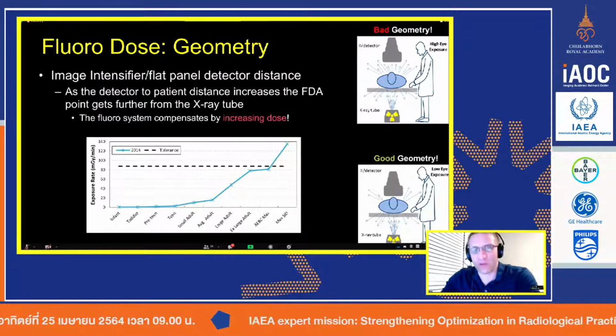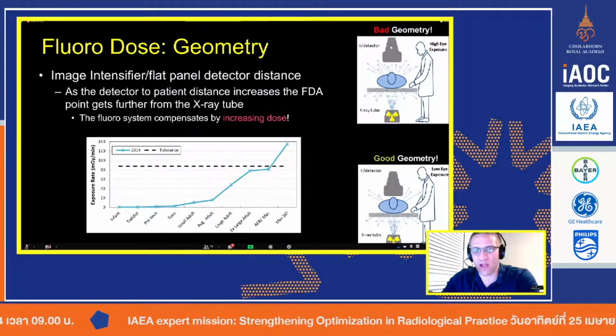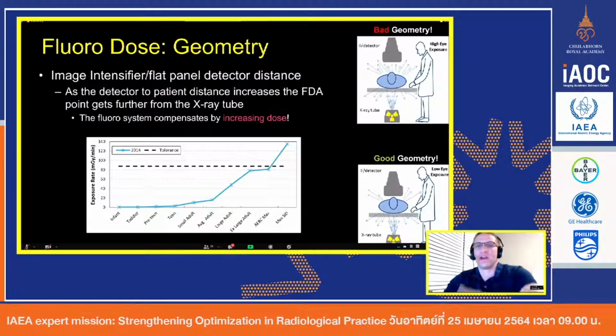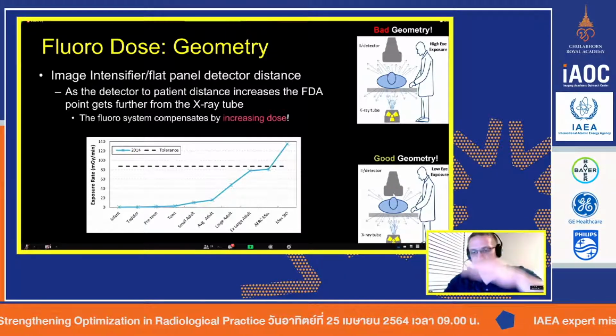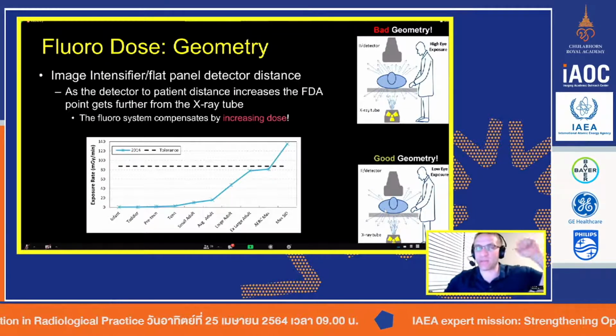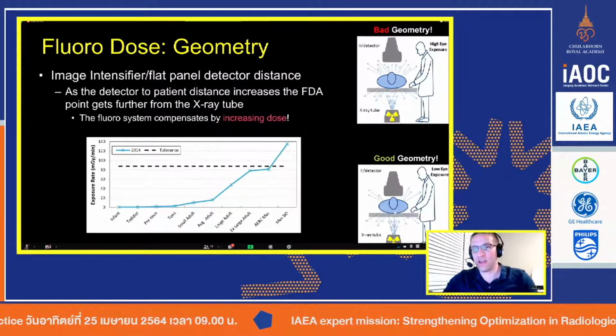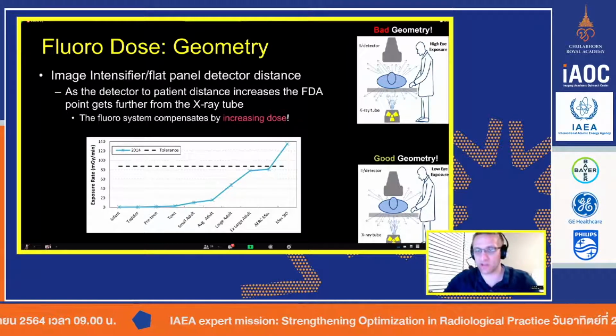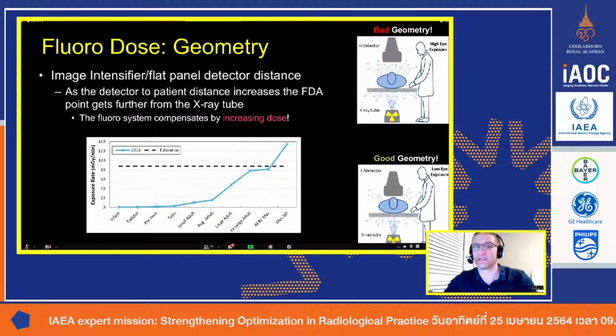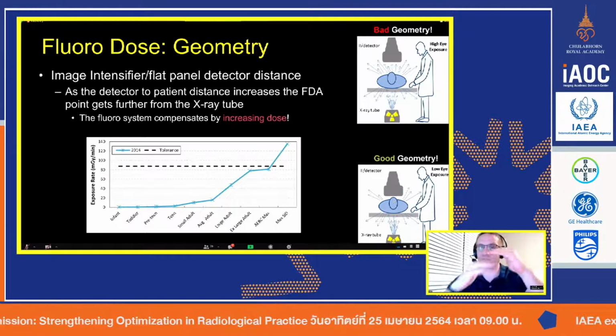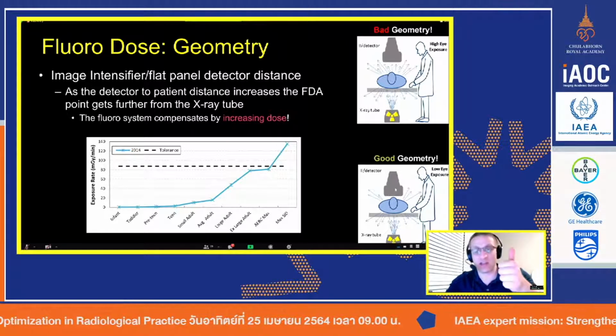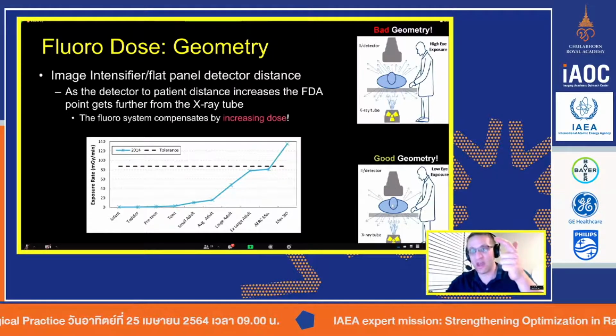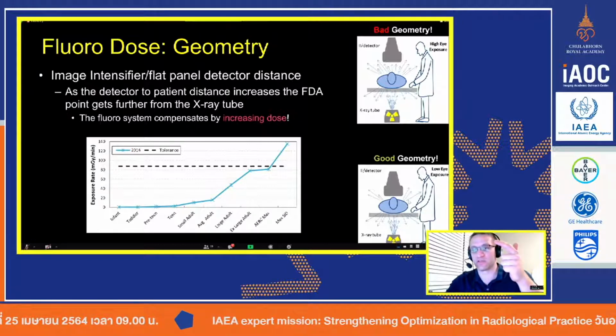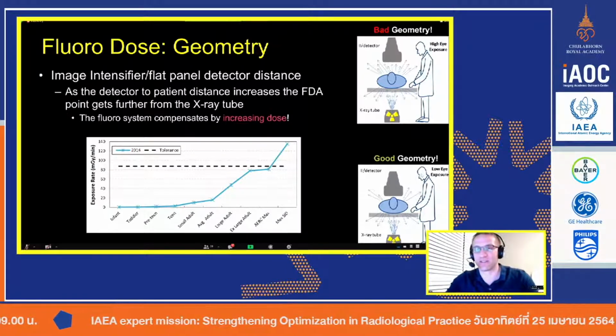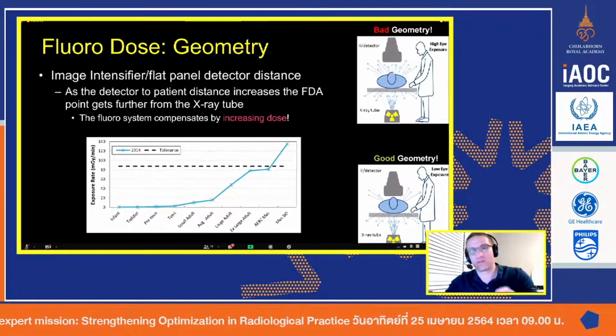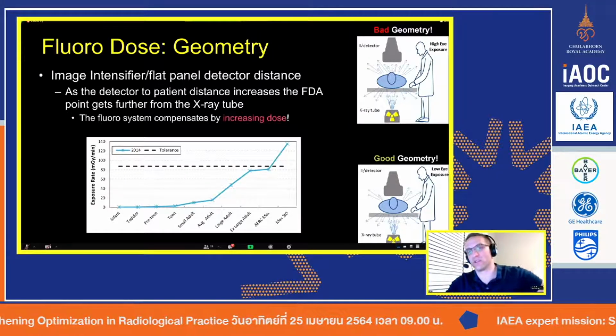So what I'm trying to say here is on these variable II or flat panel systems, on these C-arms, you do want to keep the detector as close to the patient as possible. We talked about how that is the best image quality last week. In this environment, you'll have good contrast to noise ratio, less scatter, less noise. You'll also have less geometric blur due to the magnification effect. So this will give you the best resolution and contrast. It will also give the best dose to the patient, and the lowest dose to the operator because there's just less scatter coming off the patient into your face. If you have the II high, then obviously lower image quality, lower spatial resolution, higher dose to the patient, and potentially higher dose to you.